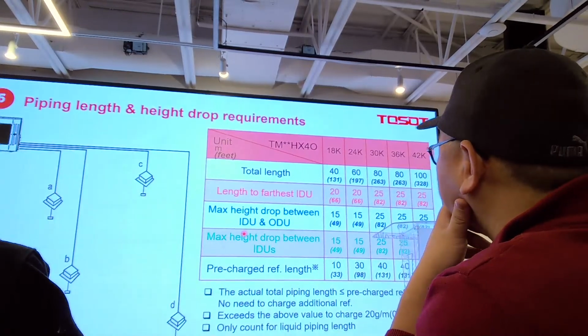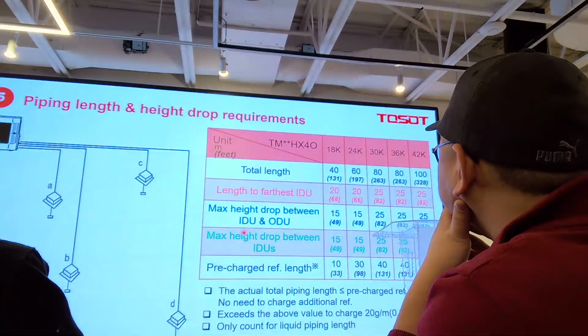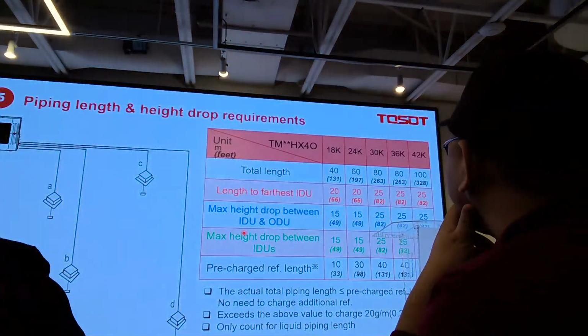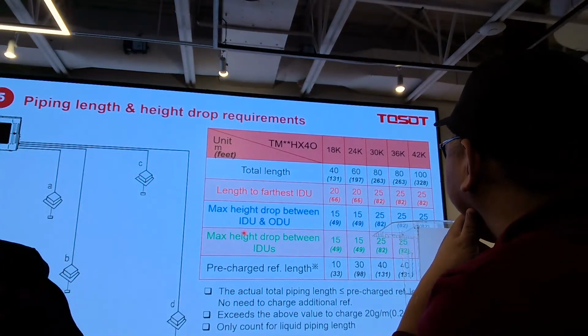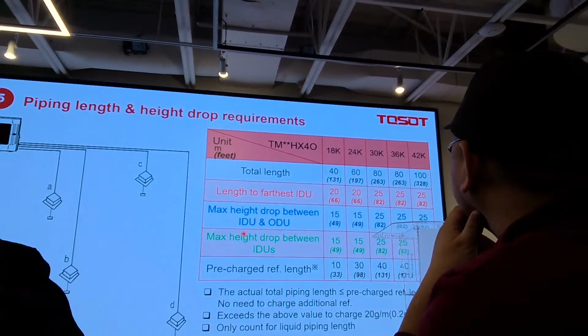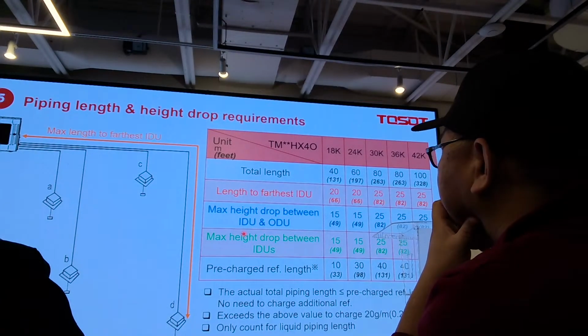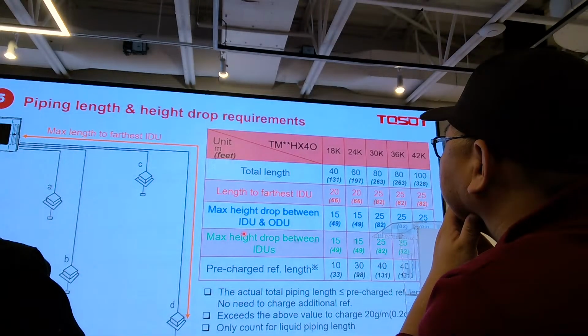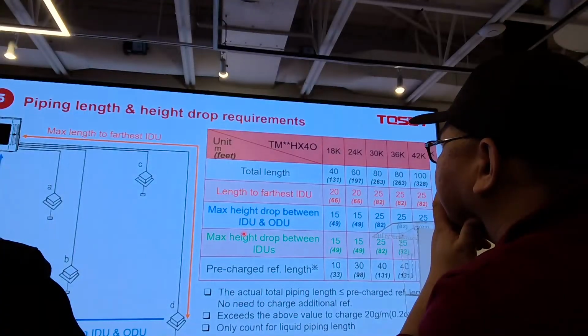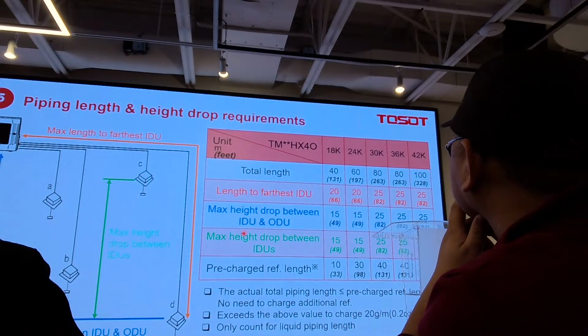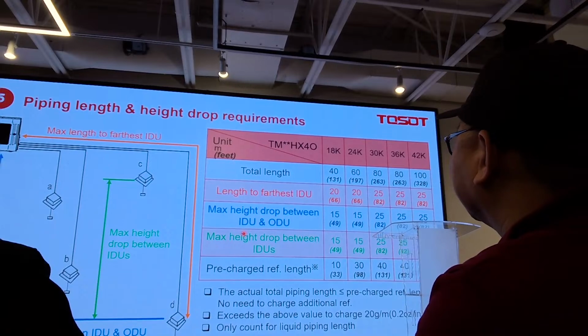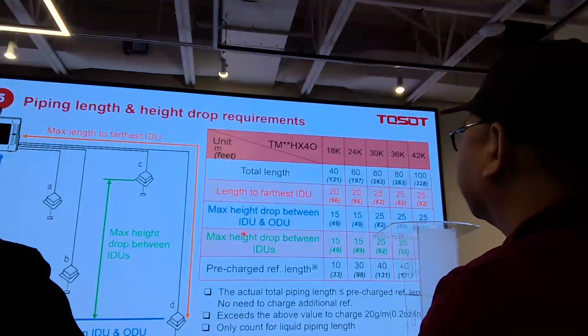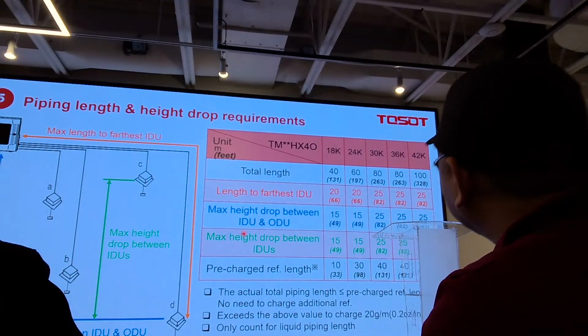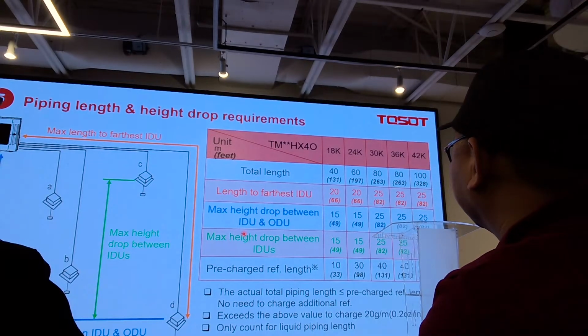Here is the piping restriction, or the limit, for the multi-zone units. We have restrictions for the total piping length and the length from the outdoor unit to the furthest indoor unit, just like this one. Here is the maximum height difference, and also the height difference between different indoor units. We also have the pre-charge amount — if it exceeds this length, you need to charge additional refrigerant.